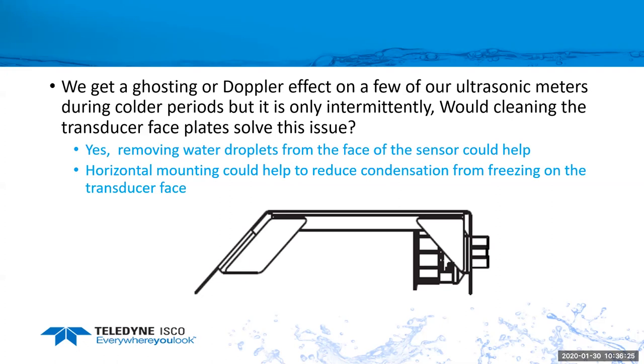So one thing you can do is we sell a horizontal mounting bracket. If you mount it horizontal, those water droplets should go to the bottom of it and stay away from the face of the transducer. So that could help minimize that problem.